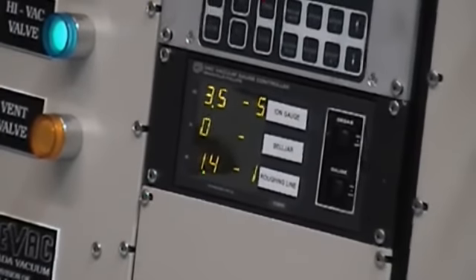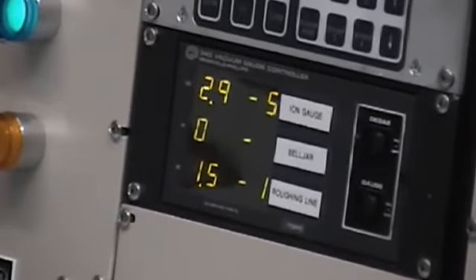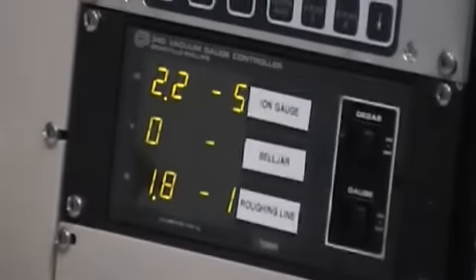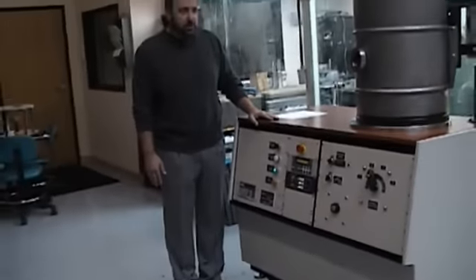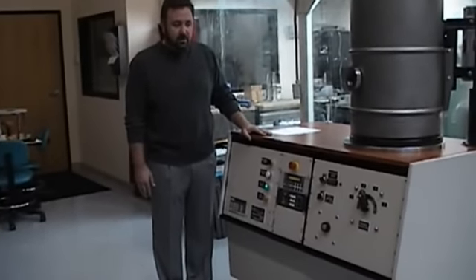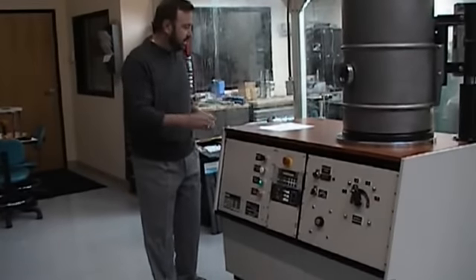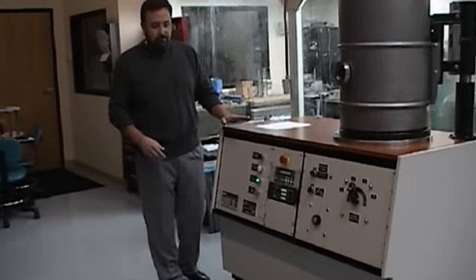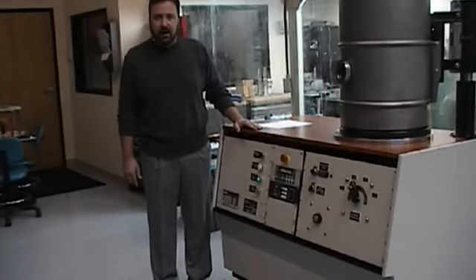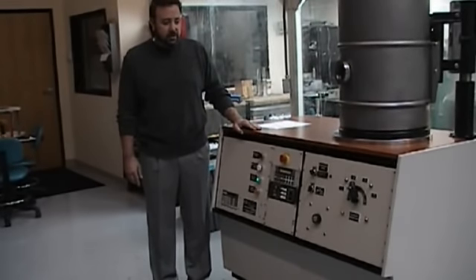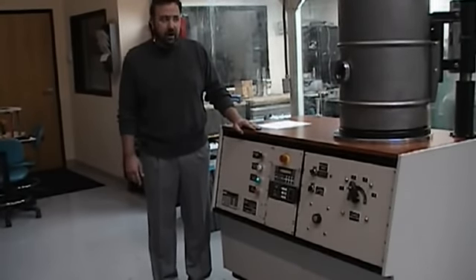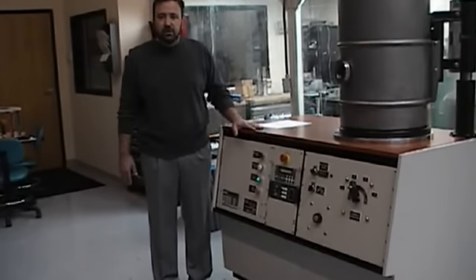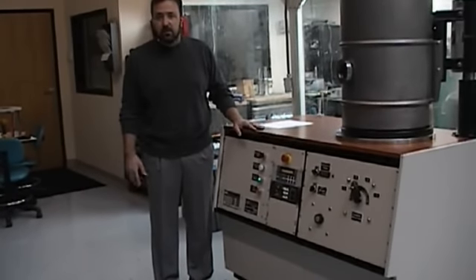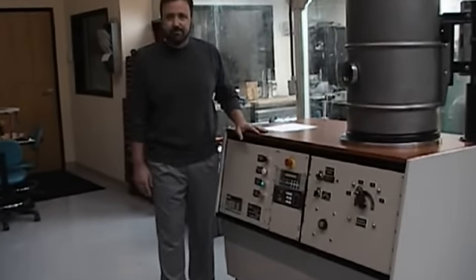On with the ion gauge, and we are down in the low 10 to minus 5 range. Instantaneously. That concludes our demonstration of the operation of the high vacuum system. What we'd like to do is take off some panels and show you the hardware inside. So we're going to go ahead and stop the tape right now and take the panels off so we can show you the insides and some of where the hardware is.